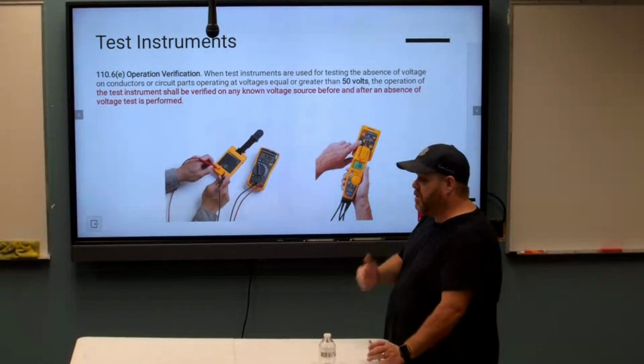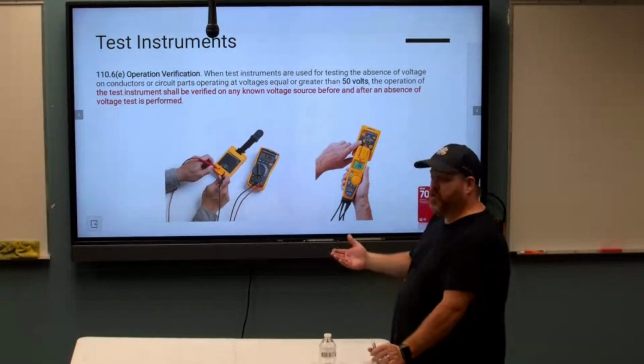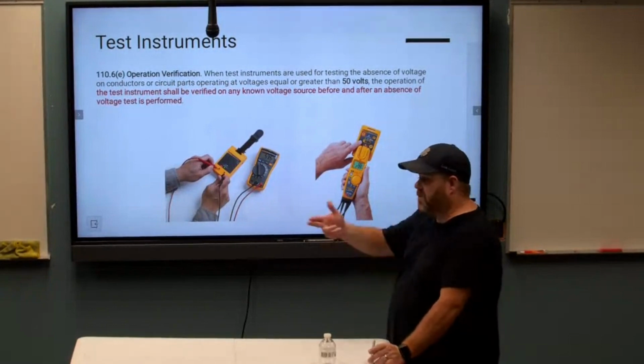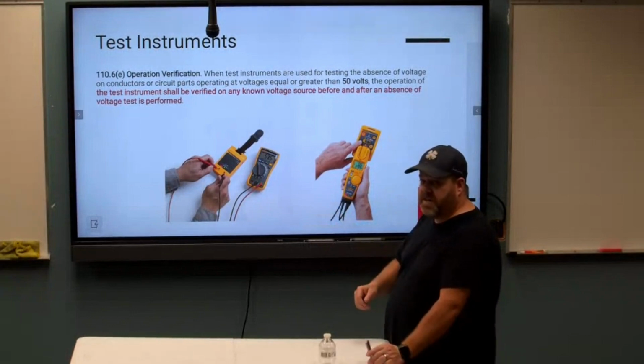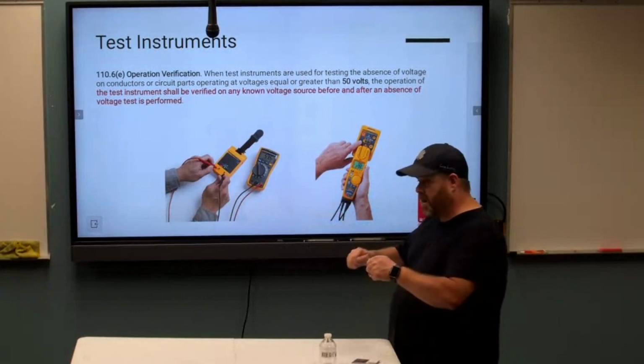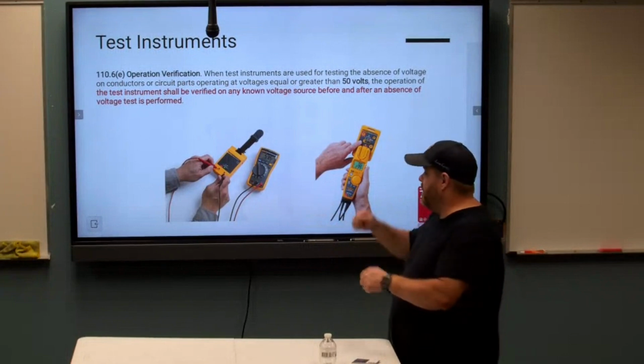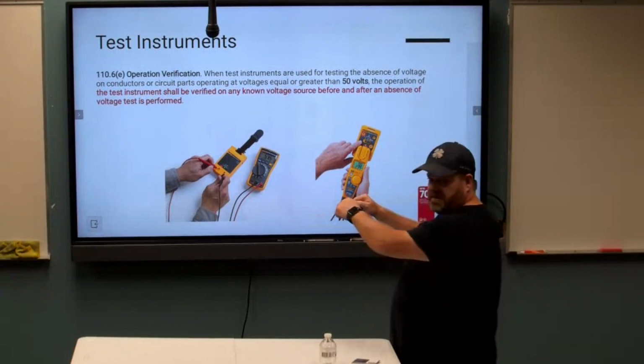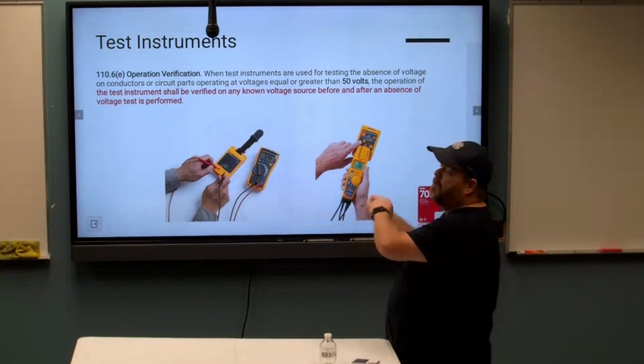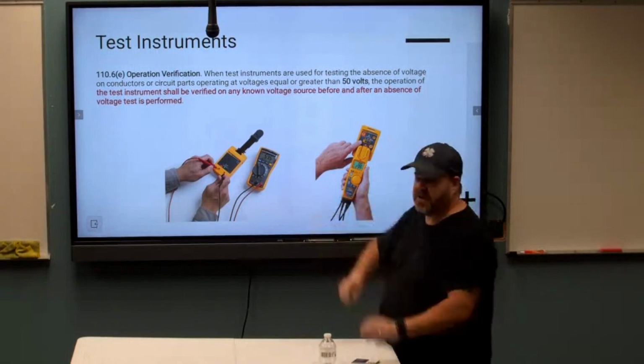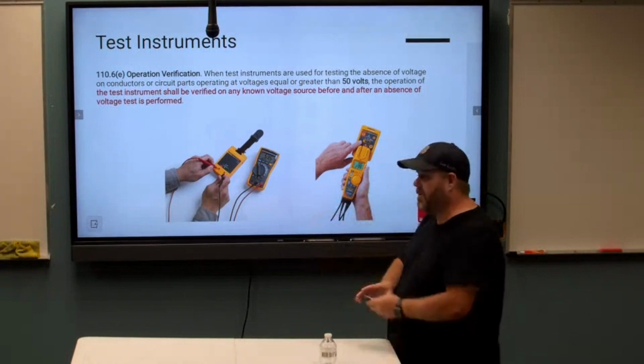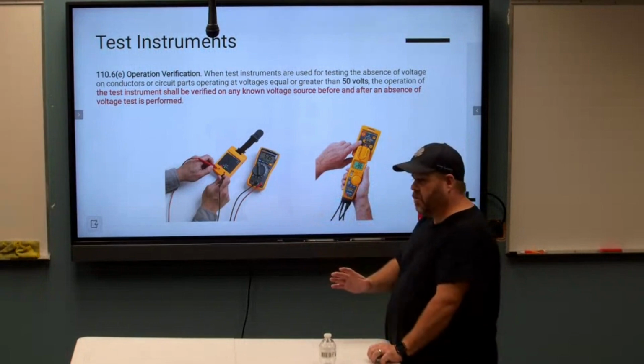So we have to go to a known voltage source like an extension cord plugged in or a receptacle on a wall and do a pre-test and make sure that meter is reading properly. Okay. Then we go do our test for the absence of voltage. And then we have to do a post-test. We have to go back to that known energy source and do a test again on our meter to make sure it's working correctly. Okay, does that make sense?